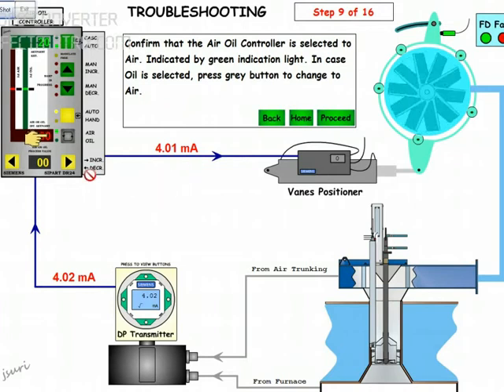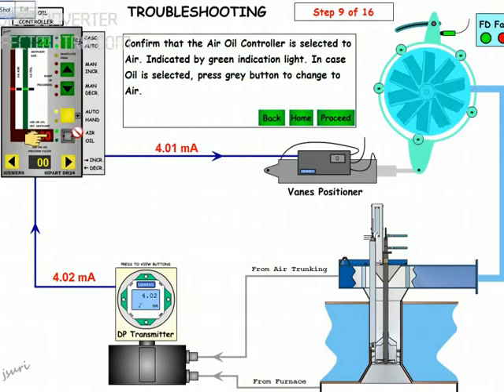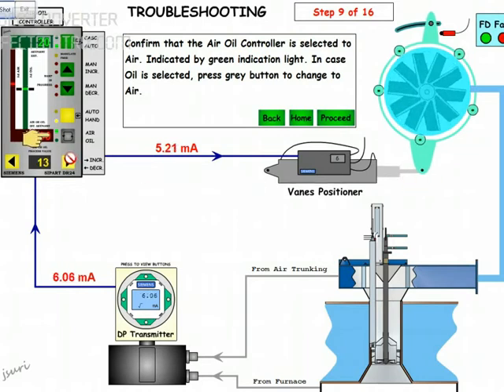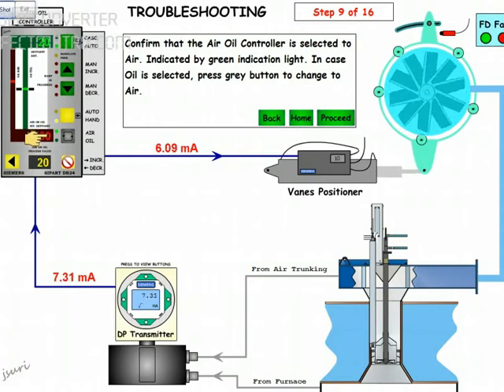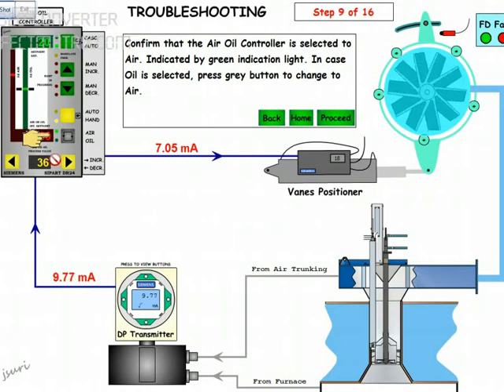Now we are going to increase the milliamps. You can see I am going to increase it. First make sure it is in the air position selected and change to hand mode so that you can operate — it was in auto. Then increase. When you increase the amps, you can see this position also moves. You can see the milliamps increasing. The vanes positioner is being pushed.